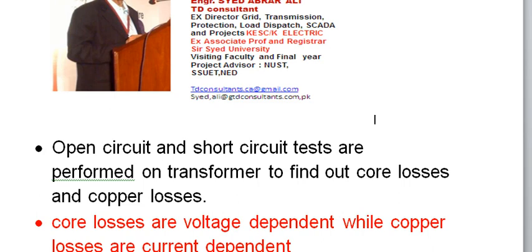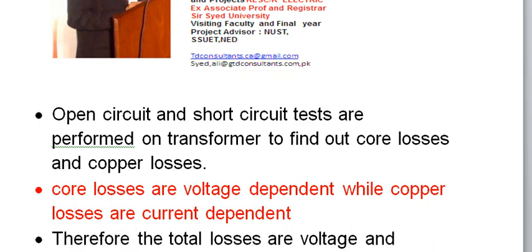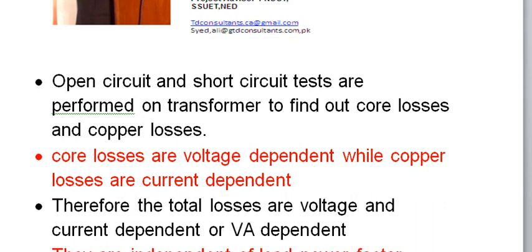The core losses are also called no-load losses, and the copper losses are also called load losses. In the open circuit test, you apply voltage to one winding and leave the other winding open. Usually the low voltage winding is used for voltage application and the high voltage winding is left open. The current drawn is very small — just enough to produce the flux, which is dependent on voltage.